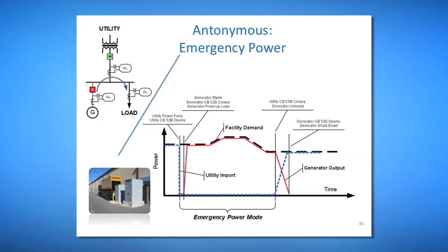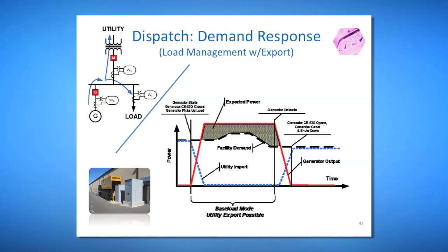Here's your demand response, and you'll notice the crisscrossing of the lines right here. Your utility demand goes down, the facility gets self-powered from the generator, and that could be like this case where you're almost powering the complete load, or this case where you're actually exporting. That's on agreement with your utility, but it can be done.